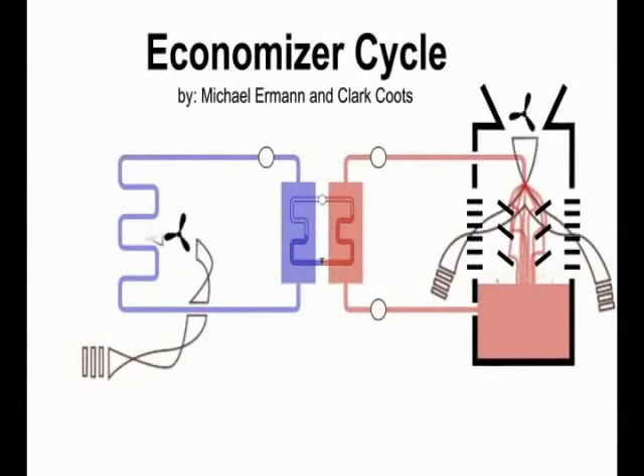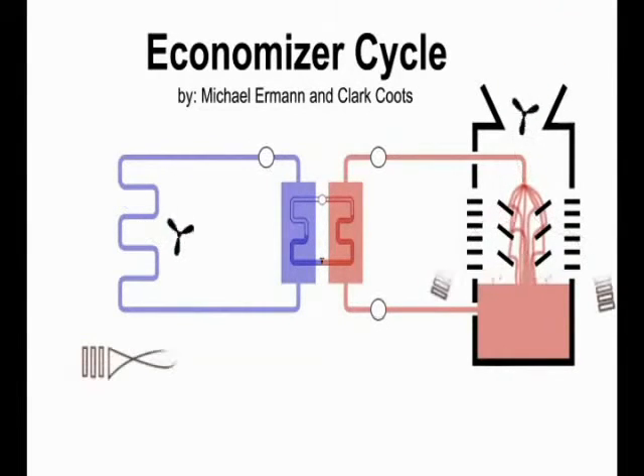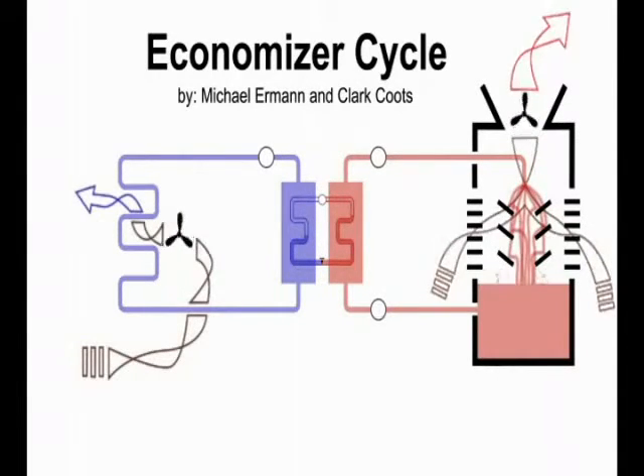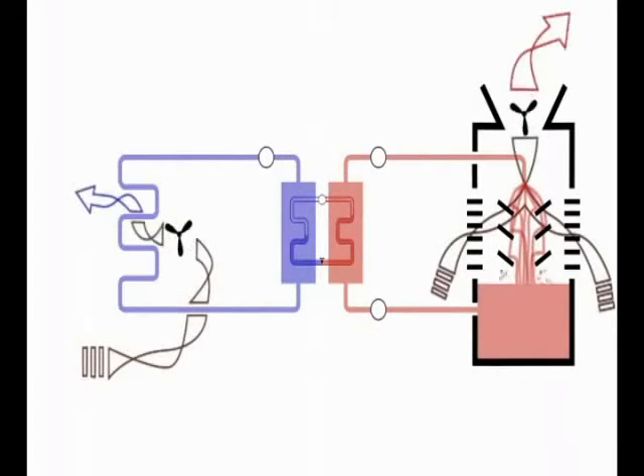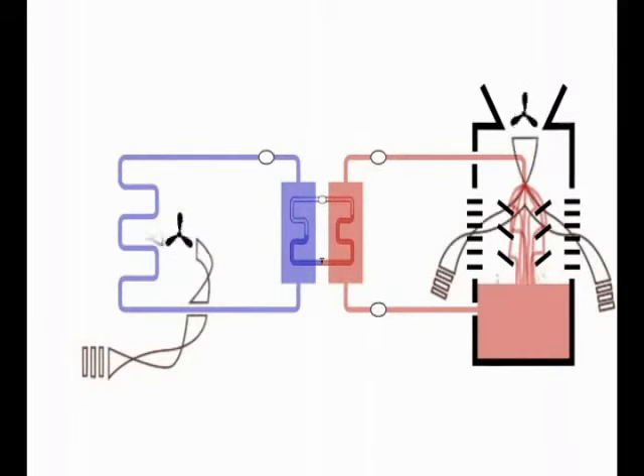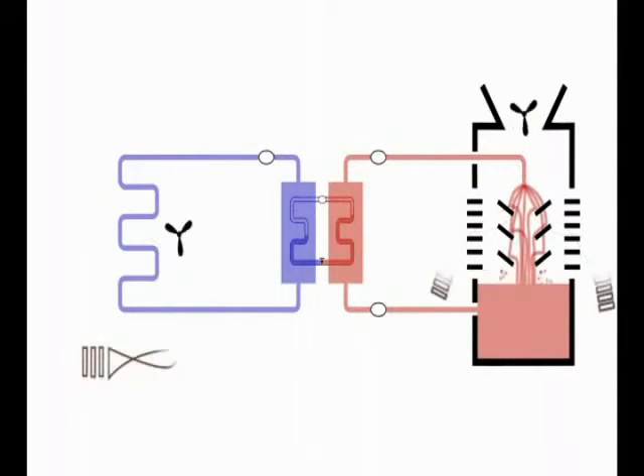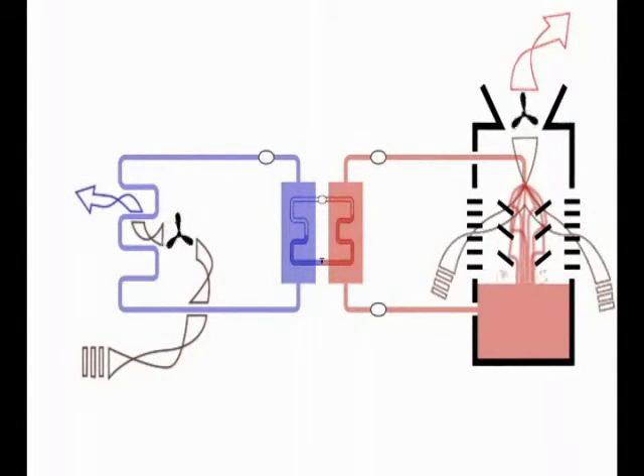Economizer cycle. Buildings, especially in the interior of large structures, often require mechanical cooling even on very cold nights. This is because the heat generated inside the building by people, lighting, and equipment will offset some of the heat losses through the building envelope.